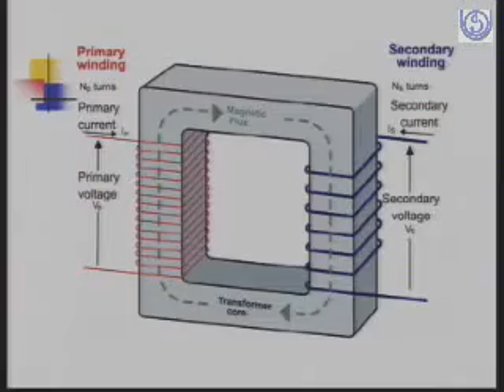So we have two types of transformers, which are the core type transformers and the shell type transformers. Core type transformers have cores with a hollow square through the center. The core is made up of many laminations of steel, and the shell type transformers are the most popular and efficient transformers, and they have a shell core. Each layer of the core consists of E and I shaped metallic sections which are butted together to form the laminations. The laminations are insulated from each other before being pressed together to form the core. The core material is generally cold rolled grain oriented steel, what we call CRGO steel. Now the steel has certain losses, and we'll come to the losses in a transformer a bit later on, but first we'll discuss the construction.